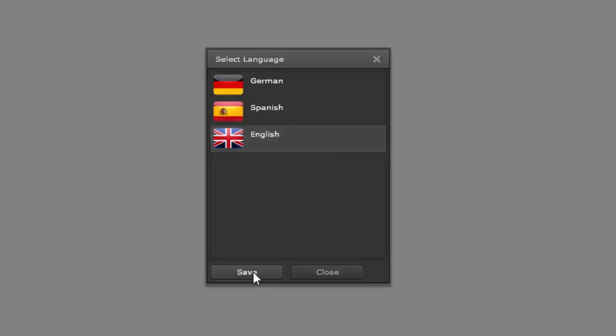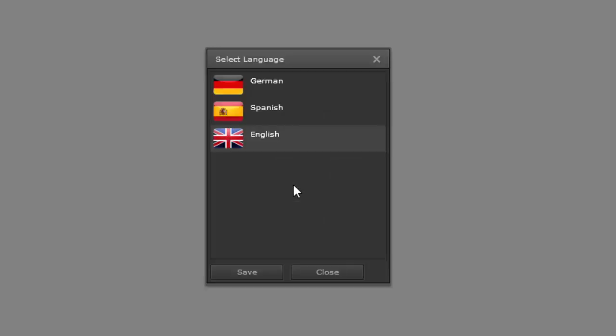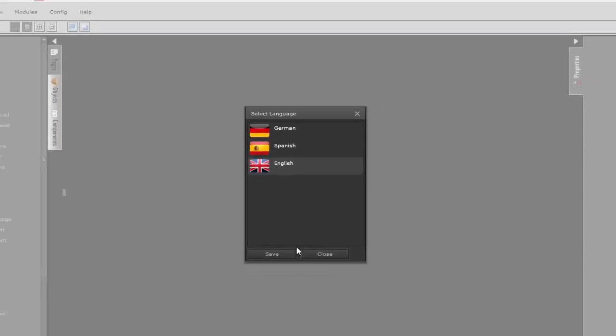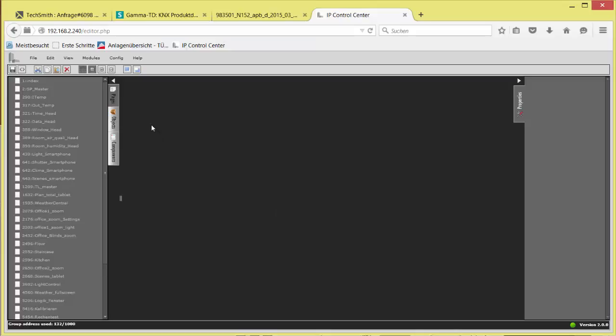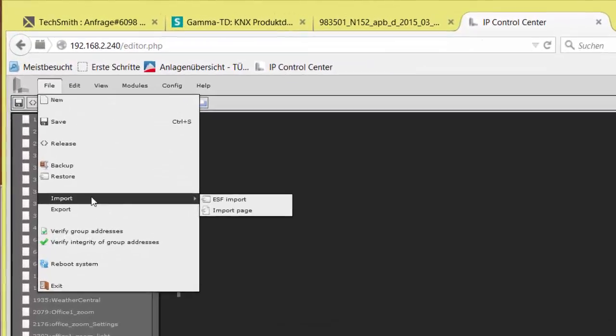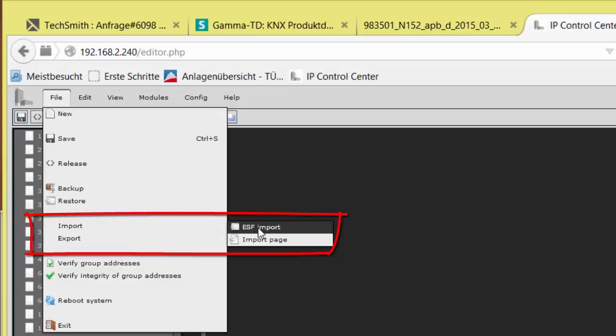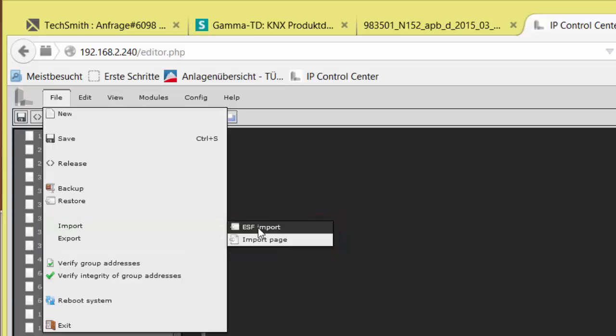Next, the OPC data file that you have created in ETS before must be imported. This data file serves, on the one hand, for replacing the short text labels of the 250 communication objects that you have already activated by ETS download, and on the other hand, for extending the number of available group addresses by up to 1000 to obtain more functionality.